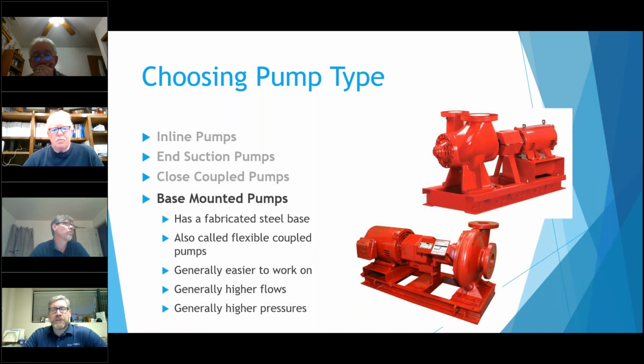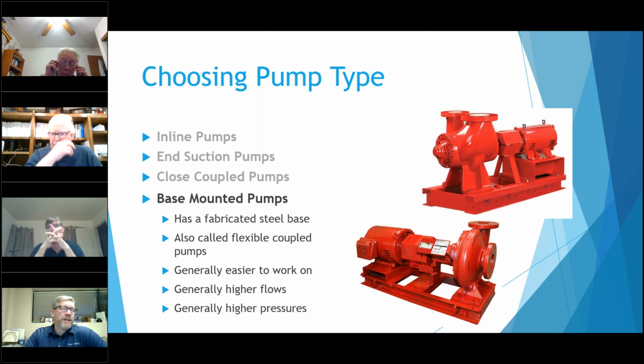And you got your base mounted pumps. The reason they're called that is because there's a nice fabricated base underneath that pump. They're also called flexible couple pumps because most of them have some type of flexible coupling in there. One big thing I do want to point out with these flexible couplers, most of them use some type of coupler that's good with the VFD. There are some out there that even B&G uses, like on their larger horizontal split case. Some of them have the Hytrel coupler. It's an orange sleeve. It's very hard. The tolerances on those are really tight, and they're just not made to use with VFD. They tend to wear out really quickly.